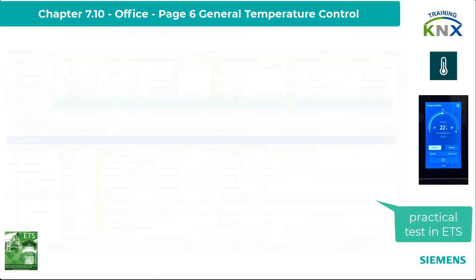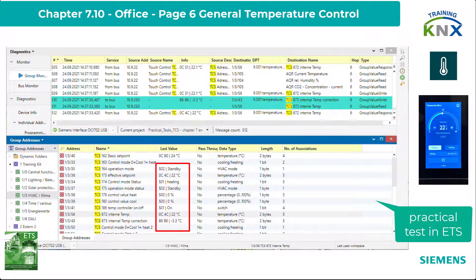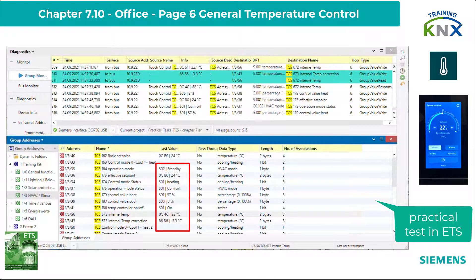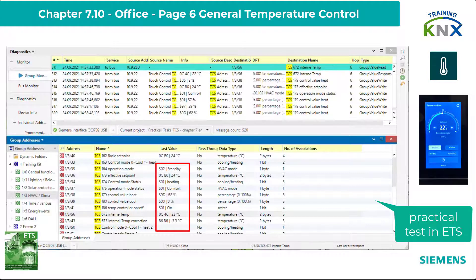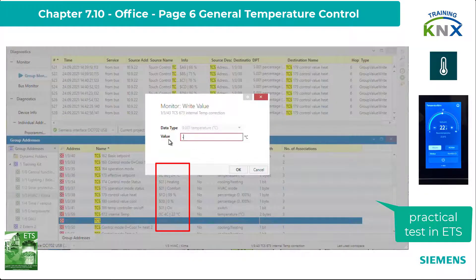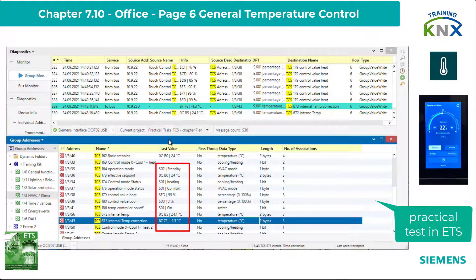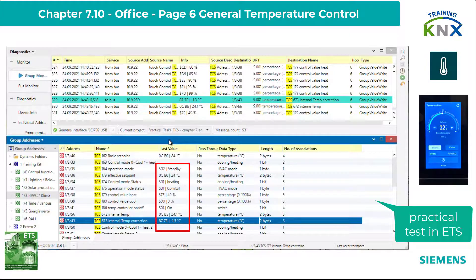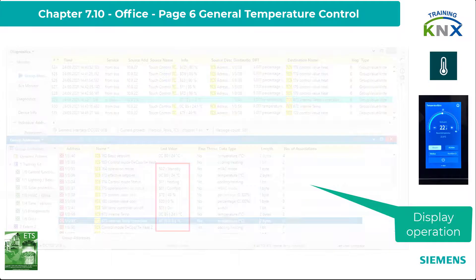Now to the test. First in the group monitor of ETS: the condition for test start is that the controller is in heating mode standby. The effective setpoint corresponds to the actual temperature value and the control variable is still zero. Now I change the operating mode to comfort — you can see that the effective setpoint value changes by plus 2 Kelvin, and at the same time the control value jumps to 57%. Now comes a time-lapse recording: after approximately six minutes, the control value is at 99%. Now I adjust the actual value via the corresponding correction object so the actual temperature is now equal to the setpoint again.